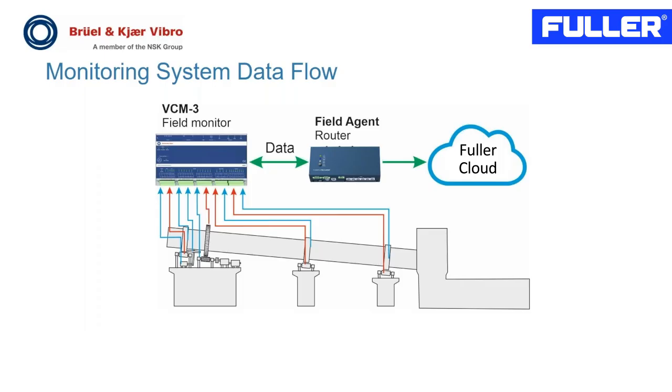We also support multiple protocols, so we could locally provide, for example, the measurement results as an OPC UA or Modbus protocol. The device itself can be used standalone. That means it doesn't need a server to operate and collect data. It has a certain memory size. The device itself is used in several thousand wind turbines and other applications, so we have quite an experience when it comes to remote operation.